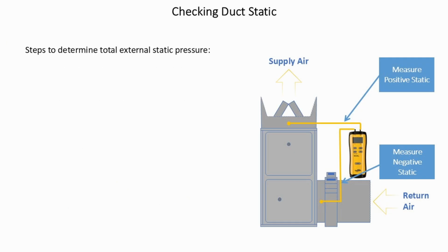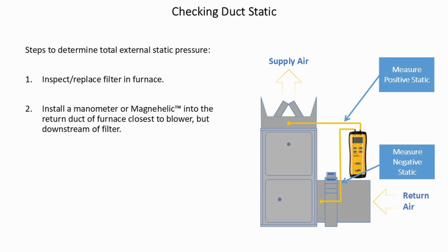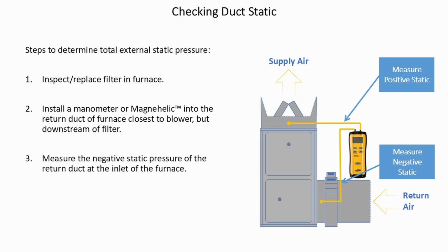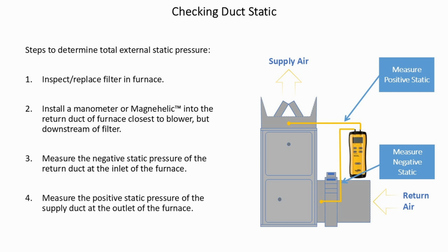Steps to determine total external static pressure. Inspect or replace the filter in the furnace. Install a manometer or magnehelic into the return air duct of the furnace closest to the blower, but downstream of the filter. Measure the negative static pressure of the return duct at the inlet of the furnace. Measure the positive static pressure of the supply duct at the outlet of the furnace.